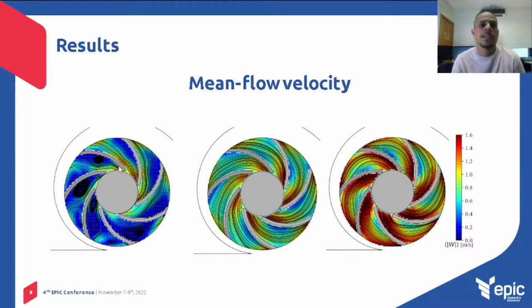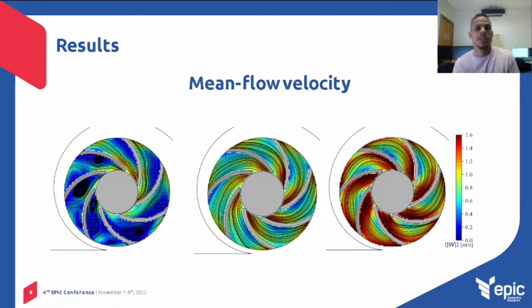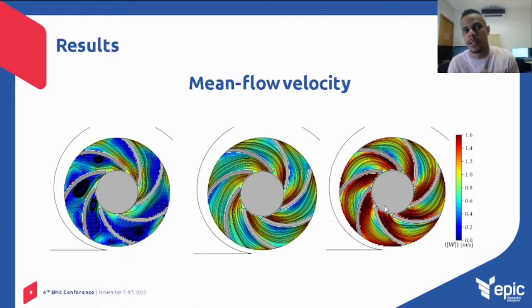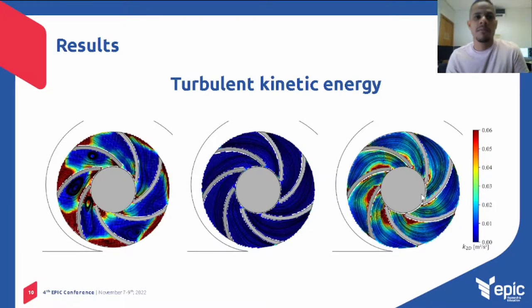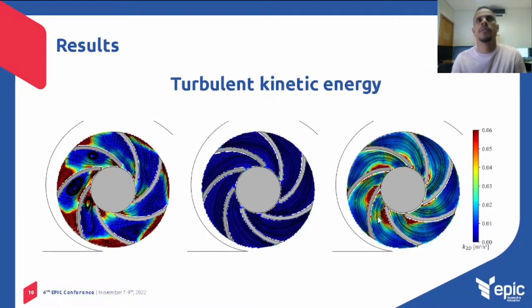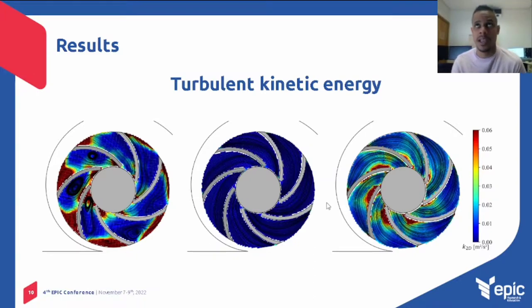This recirculation zone is associated with a secondary flow of the boundary layer and also apparent forces present in the rotating reference frame. In addition, at low flow rate, the formation of small flow instabilities is noted. Here I present the contour plot of the turbulent kinetic energy for 0.3 BEP, 1 BEP, and 1.5 BEP. The design BEP range shows the lowest TKE, which is associated with a more efficient flow rate.